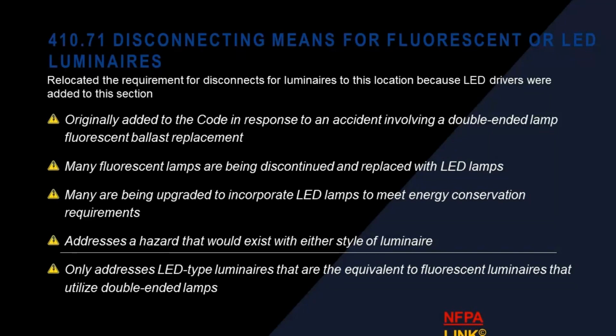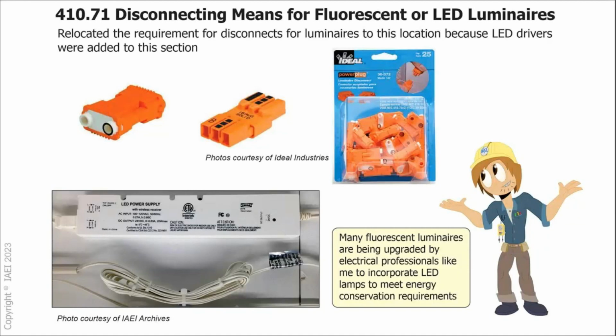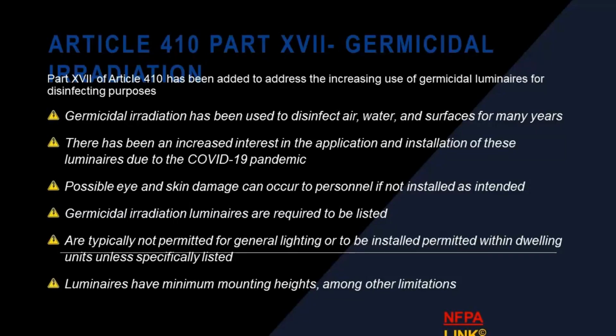All right, 410.71, disconnecting means for fluorescent or LED luminaires. This basically relocated the requirement for disconnects for luminaires to this location because LED drivers were added to the section. So really this code change is not really a change, it's more of a relocation. All right, here's our disconnects for luminaires. This counts for fluorescents or LEDs. Okay.